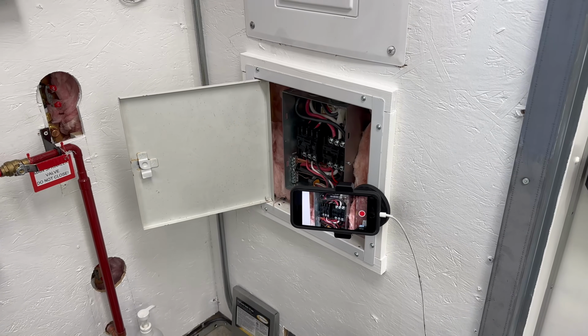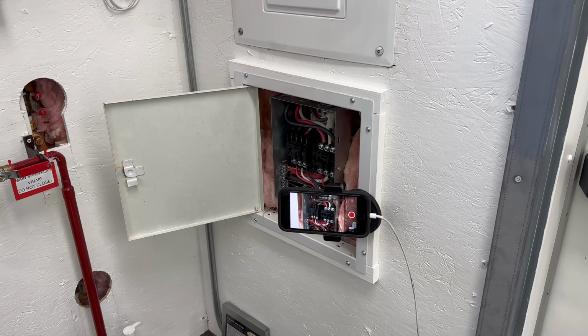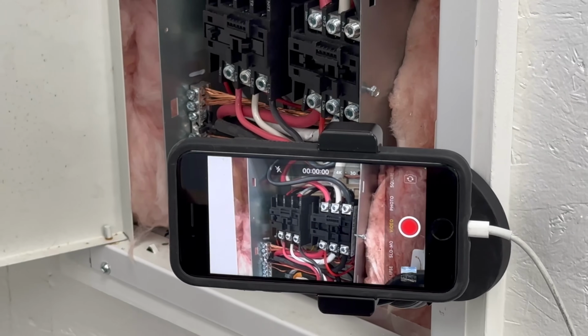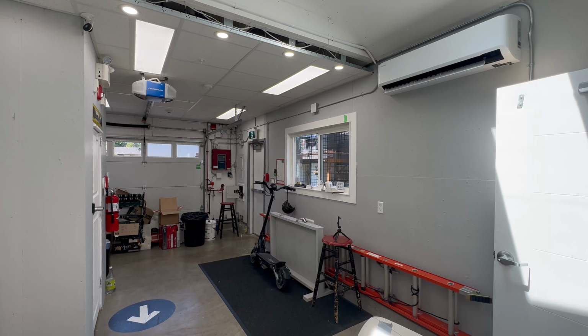I will now simulate a power outage. I have a couple cameras mounted. I have one on the transfer switch here. My main camera view will be right here, which will show the emergency lights covering the time period before the generator starting, and you will be able to see the fire door will shut when it loses power. I will now go into the house and turn off the breaker that is feeding power to this building.